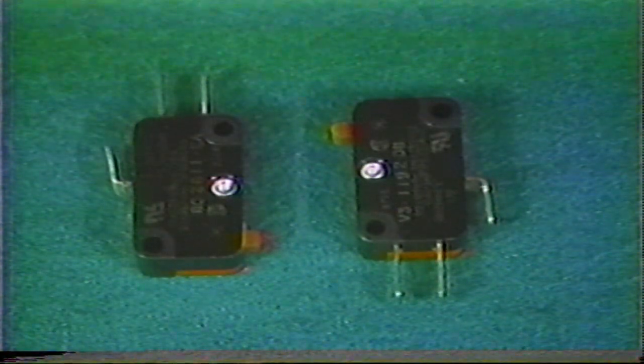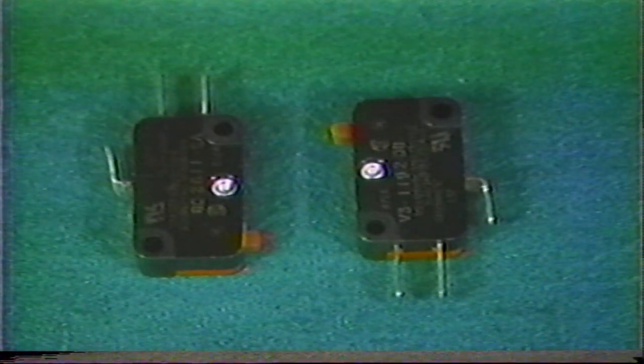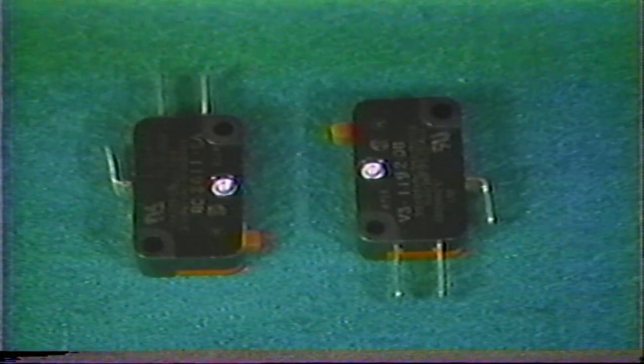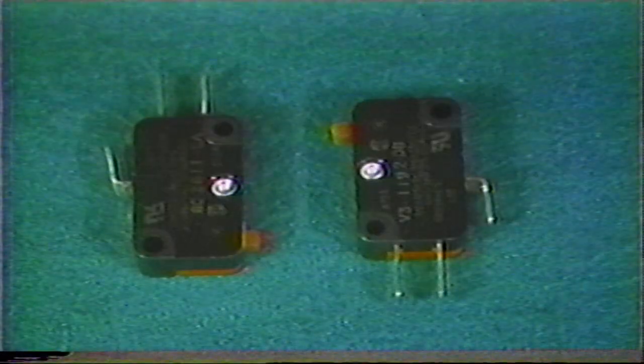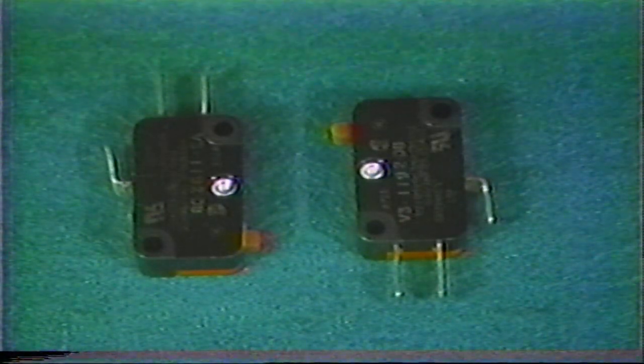Do not try to bypass or defeat the door interlock switches and operate the oven with the door open. This can damage the oven and expose you to high microwave energy. When reassembling the oven, make certain there are no extra parts. All screws should be properly replaced and a leakage detection performed.